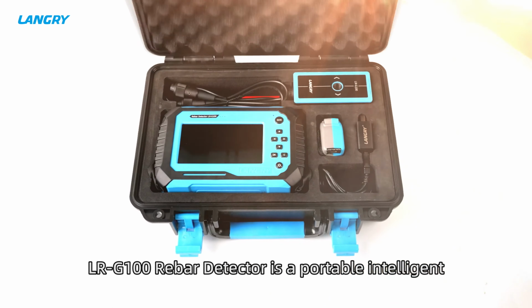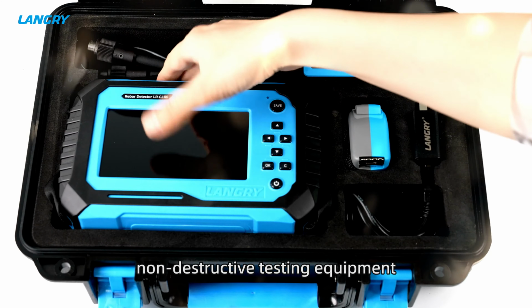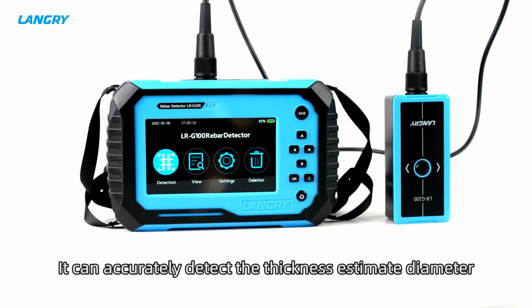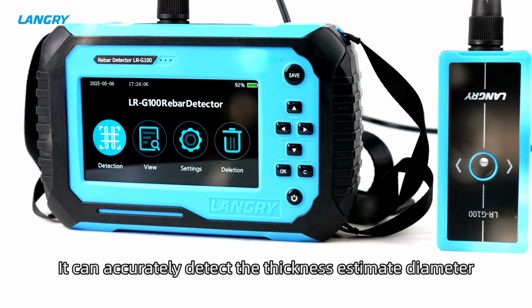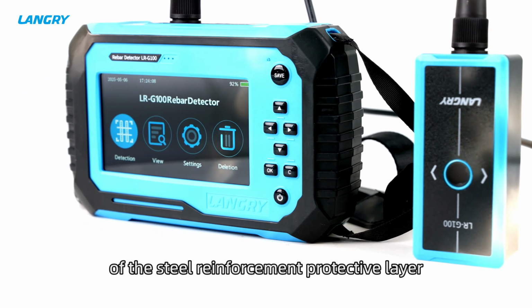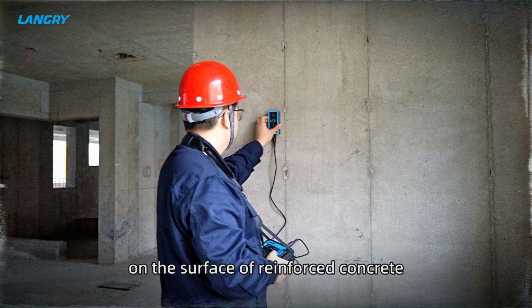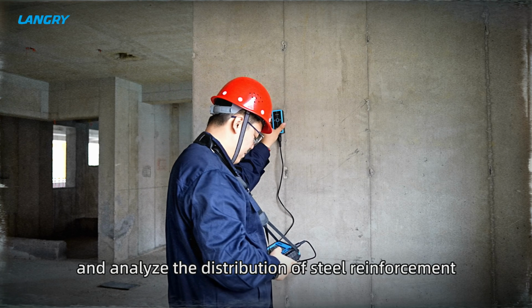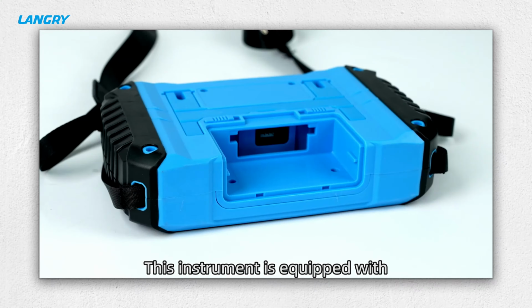LR-G100 Rebar Detector is a portable, intelligent, non-destructive testing equipment, mainly used for structural testing of reinforced concrete. It can accurately detect the thickness, estimate the diameter of the steel reinforcement protective layer on the surface of reinforced concrete, and analyze the distribution of steel reinforcement. This instrument is equipped with a large-capacity pluggable lithium battery, providing super long battery life.